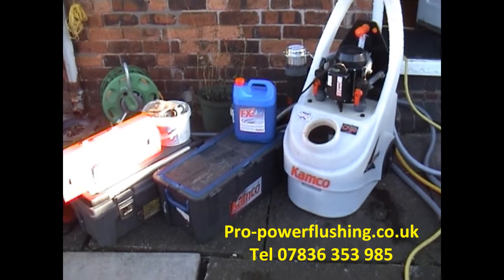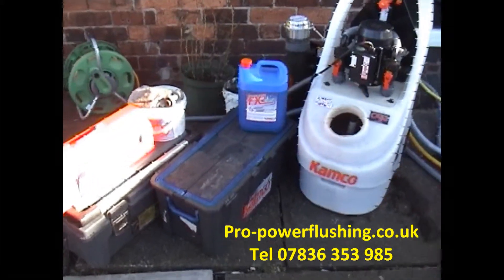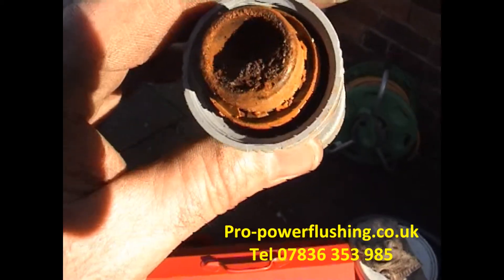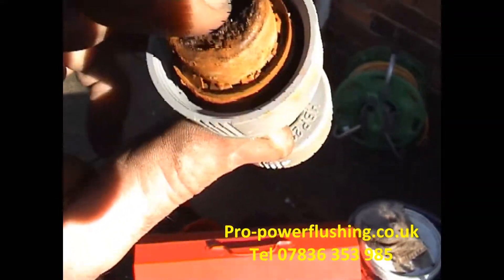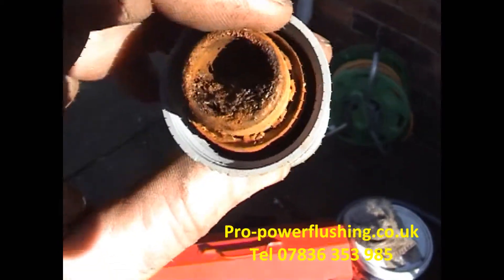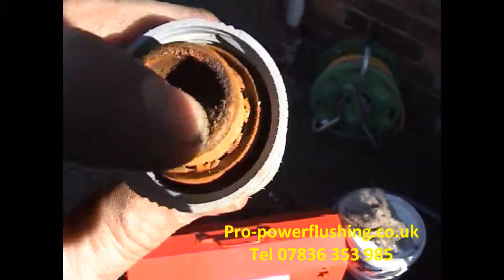We're just going to show you a piece of pipework we actually took out of a property yesterday. It was in a very, very bad system. If you can see that, it's absolutely full of rust. It's actually gone solid as well — we had to actually cut this bit of pipework out. It was one of the worst systems we've done for a long time. We actually had the power flush machine on full flow on this particular bit of pipe with the chemical in, the Kamco FX2, but obviously it just wouldn't shift it. It's just gone absolutely solid.